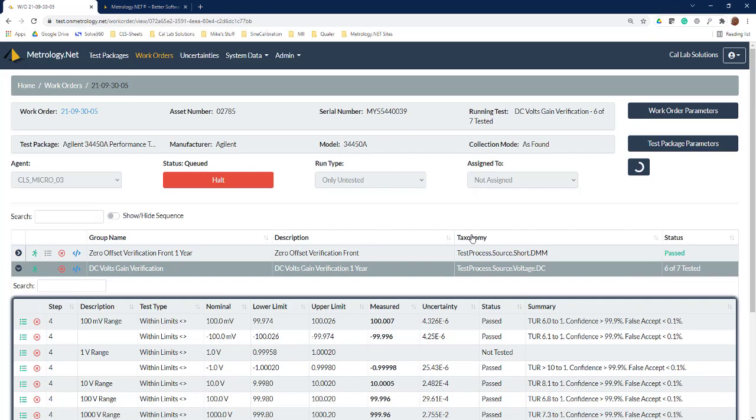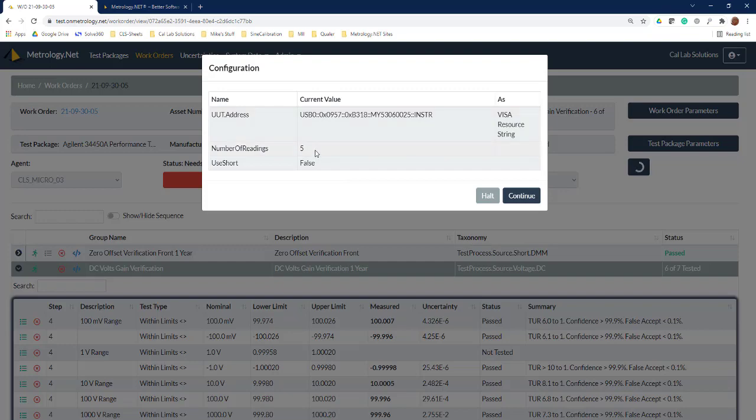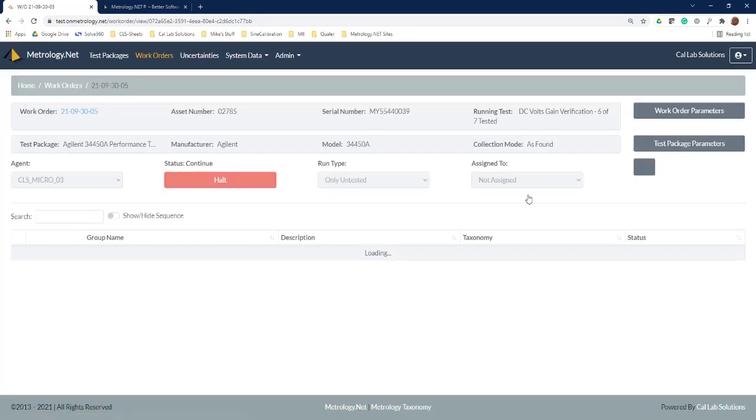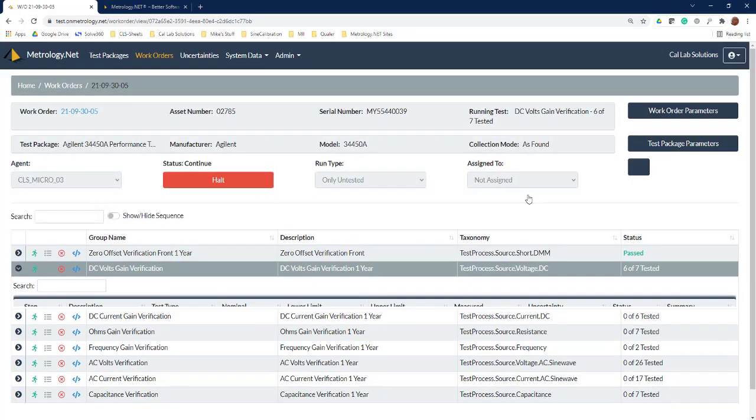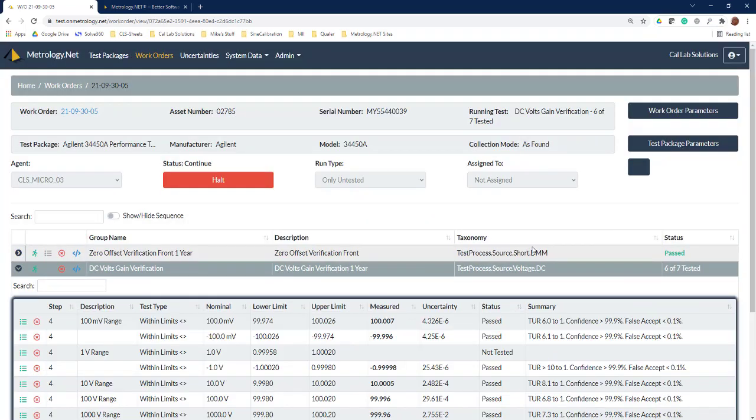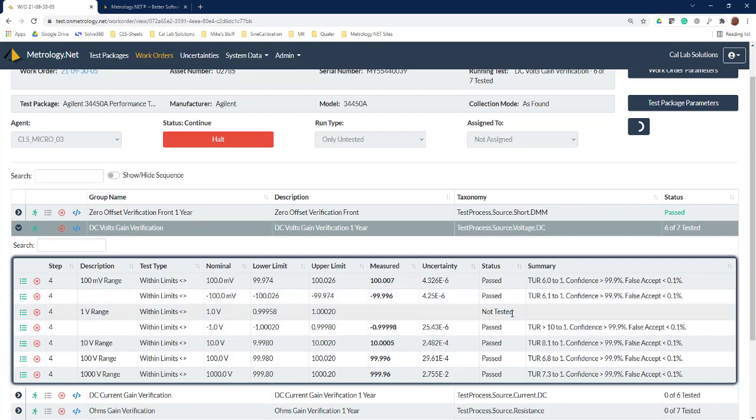We're going to go back through the same process. It's going to ask us to configure the things for our workstation. You can see here we can set the UUT, set the number of readings, hit continue. It's going to reset the equipment again, and now you watch this—it's going to do just this one data point and then it's going to get out of there.